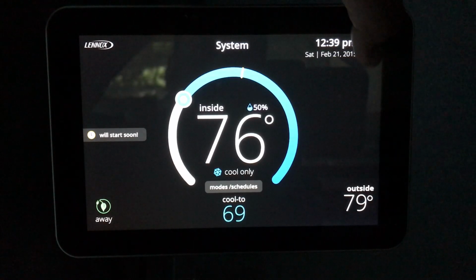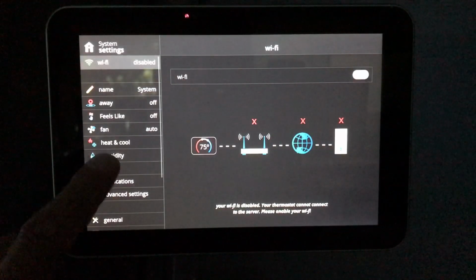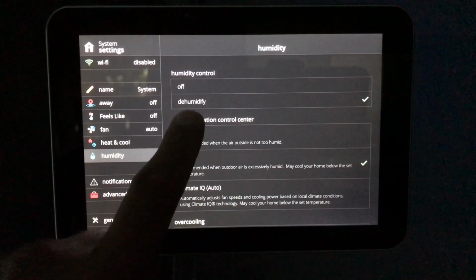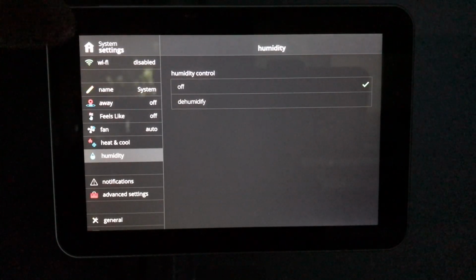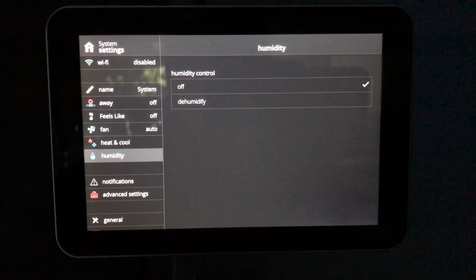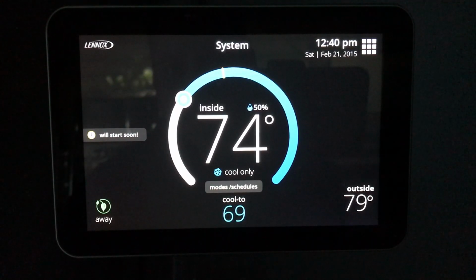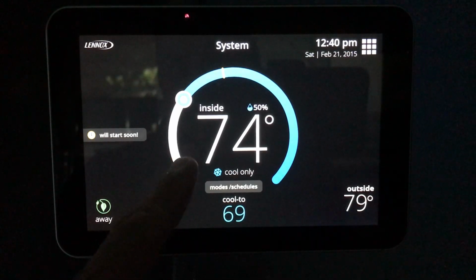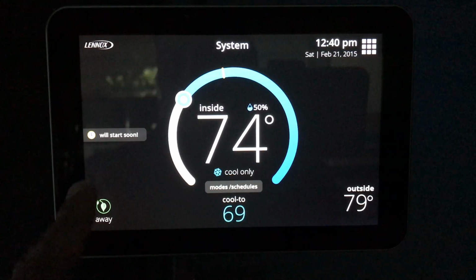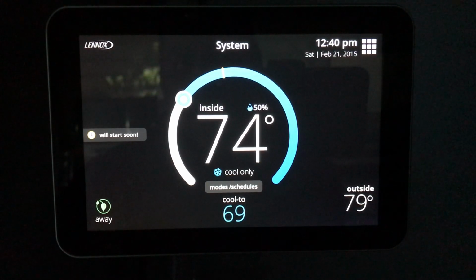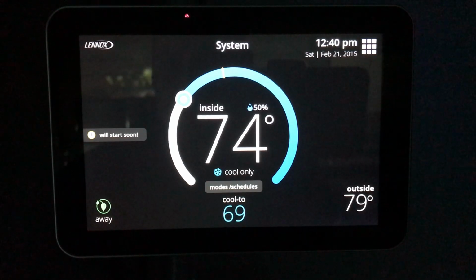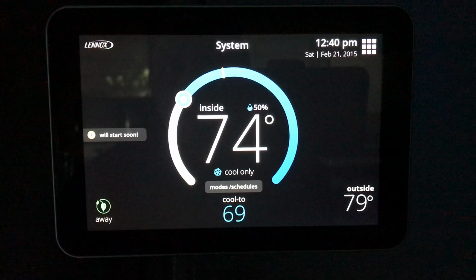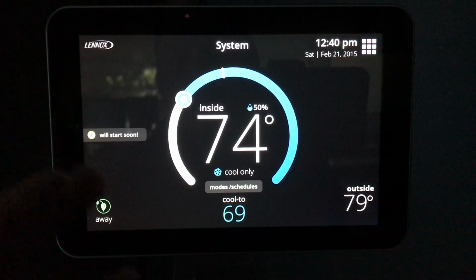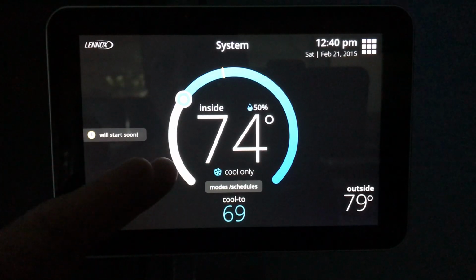The other thing I just want to remind you about is if you ever go to a home and you see this humidity setting right here where they've got it turned on to dehumidify, we want to turn that off. Now a lot of customers will find that function on their own and turn it on because we all want dehumidification during the summer months. But what that changes this controller to is it will target and overshoot your temperature setting and start to target only the humidity setting along with it. So most folks don't sit at home and say, honey, it feels like it's 60% humidity in here, let's get it down to 50. So I would just give them the assurance that let's focus on achieving the set point of the exact temperature they're comfortable at.